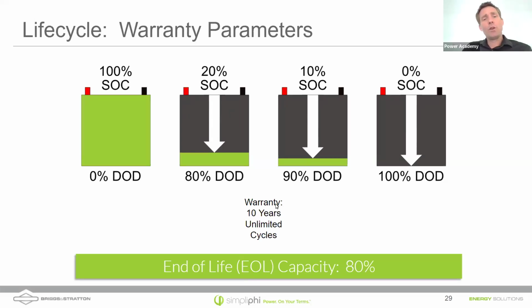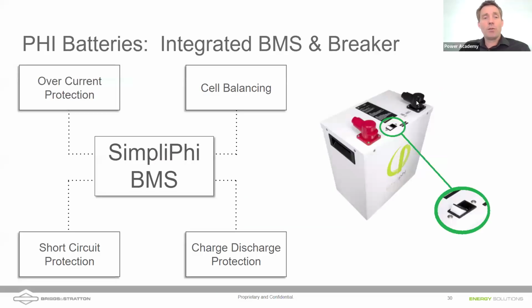But on the bottom end of things, we do see a big difference. If we're only discharging continuously down to 80% depth of discharge, leaving about 20% in the battery, we expect about 10,000 cycles. If we discharge all the way down to 90% depth of discharge, I believe the number is 6,000 cycles. And at 100% depth of discharge every single time, we're looking at more like 3,500 overall cycles.